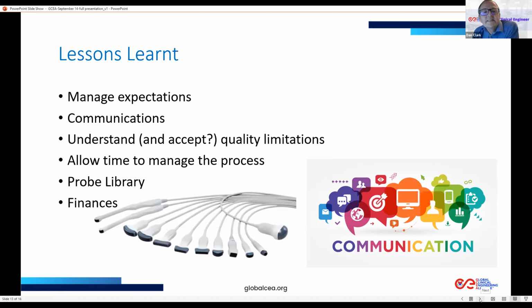So one of the things that we did and lessons that we've learned is that we've overcosted so that we can provide additional probes in certain clinical areas to create, if you like, a virtual library of probes which are already tested, they're clean and ready to go. In this way, as soon as there's a problem with the probe, a break or damaged probe, we can immediately swap it out for a new one out of our equipment library stock, while we then take the time to service, repair and retest the damaged probe.